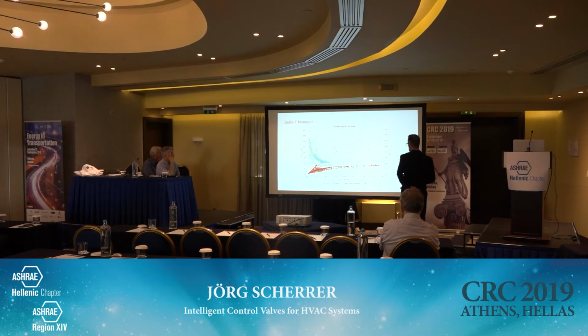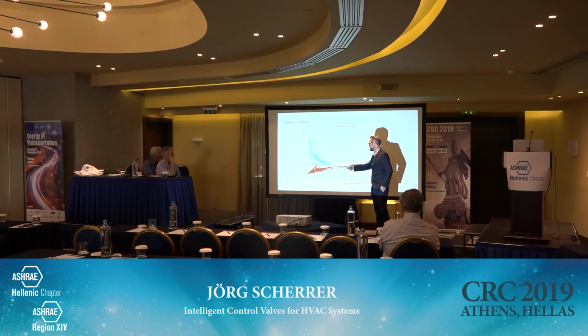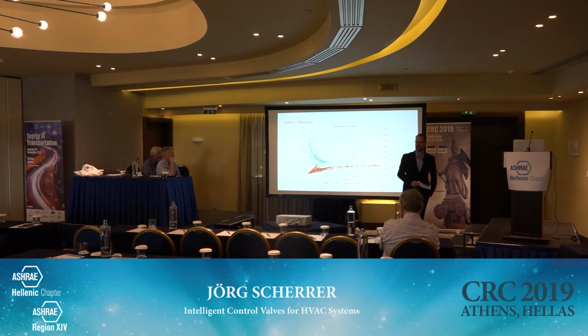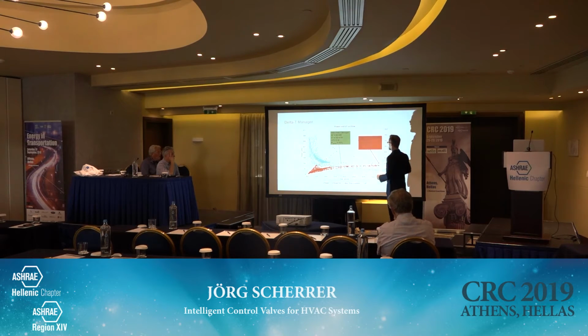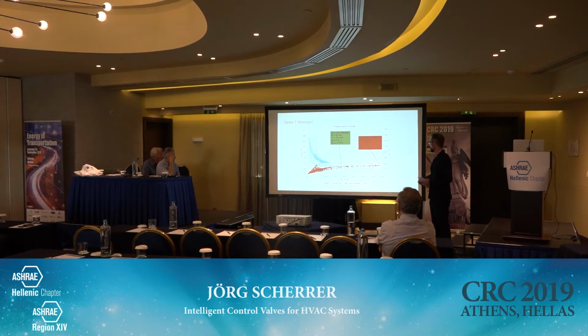Now when you look at this curve, the same power output I can get here with 18 cubic meters per hour. I have the same comfort in my room, the same comfort at the heat exchanger, the same power at my heat exchanger, but instead of running the pump at 100% and 38 cubic meters per hour, I can reduce the flow to 18 cubic meters per hour. So with an intelligent delta T management, we can reduce the pump to 11% instead of 100%, and all these operating points here on the right side would be avoided.